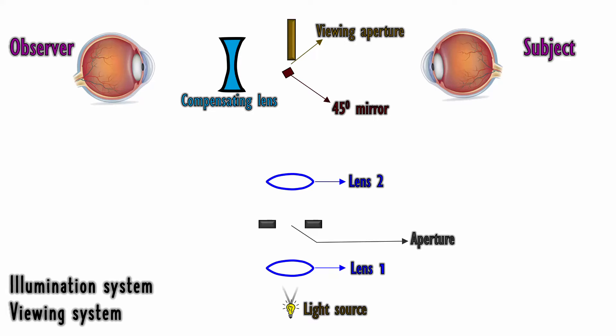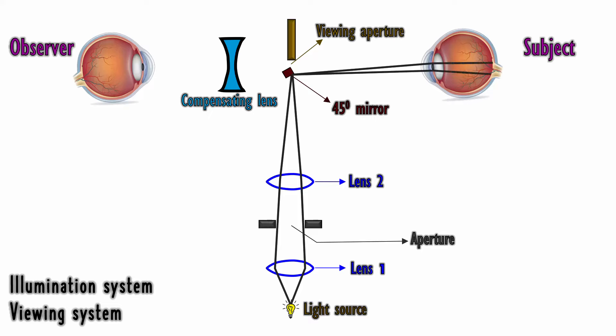Light rays from the lamp are converged slightly by the first lens, pass through the aperture, and are focused by the second lens onto the mirror, which then reflects light into the patient's eye to form an illuminated area on the patient's retina. Some of the reflected rays from here pass out of the patient's eye through the viewing aperture and compensating lens of the ophthalmoscope onto the observer's retina.